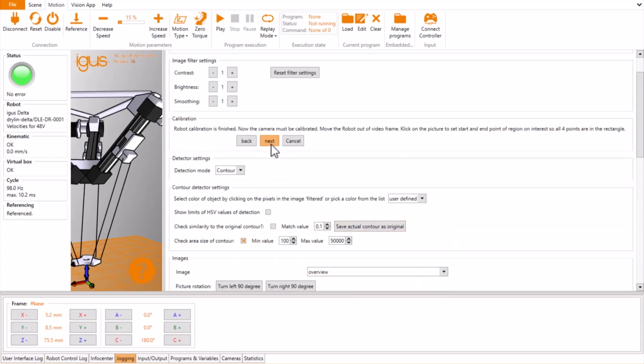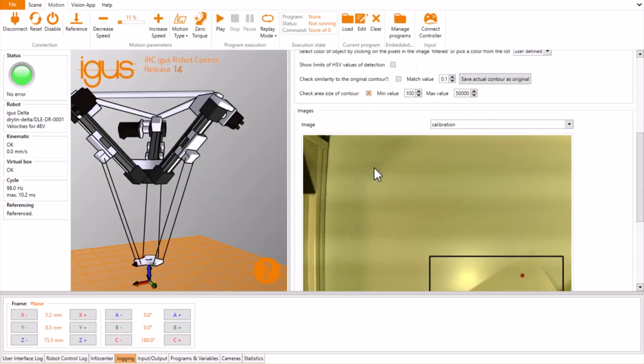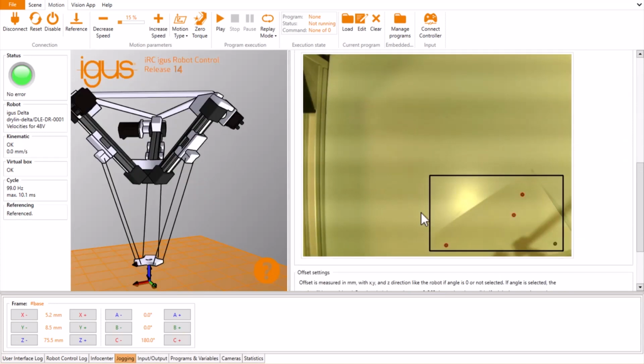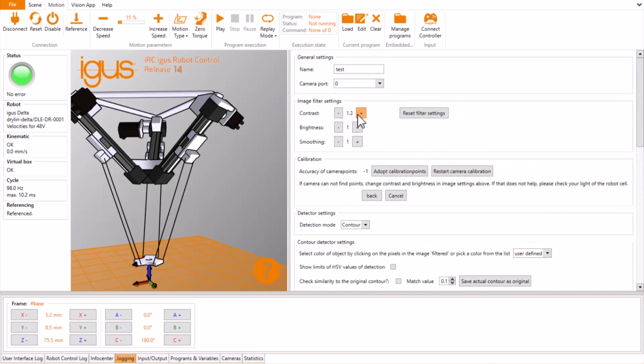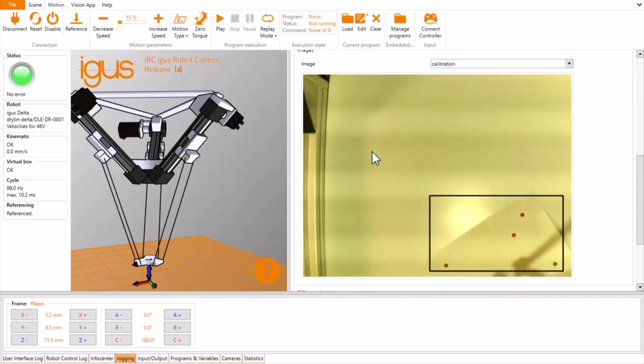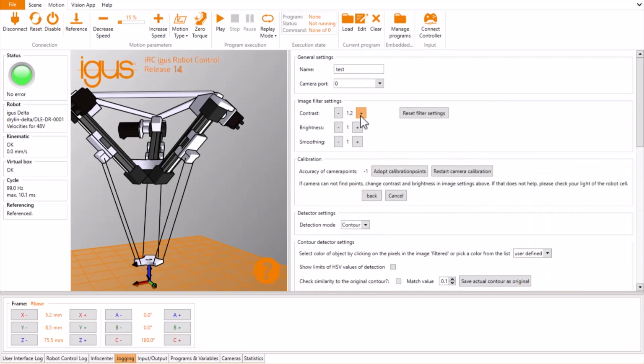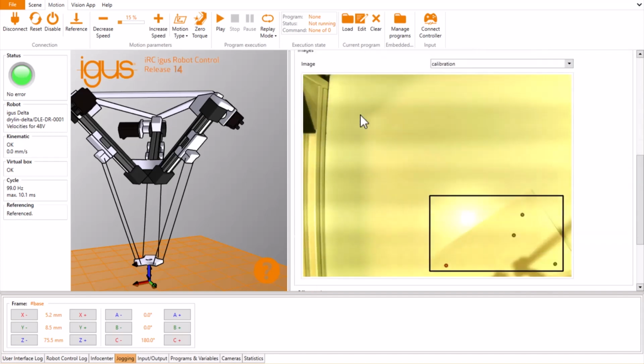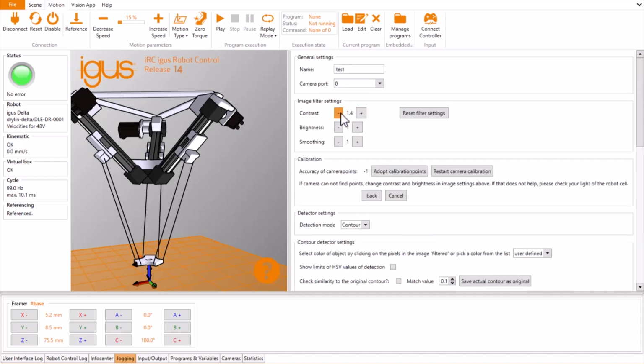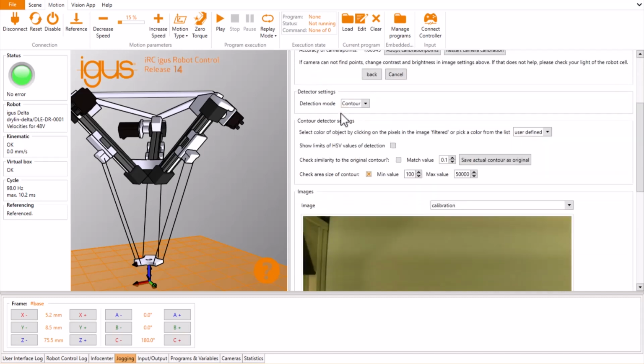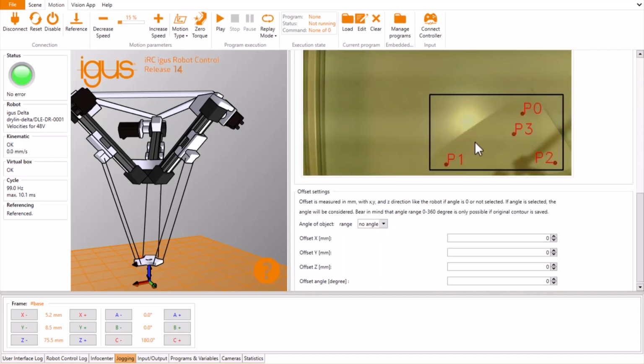The app now tries to find the 4 black dots on the camera image. When the camera has found a dot, it is initially outlined in red. You can see that the camera has already identified some of the dots, but not all of them. Use the image filter settings to change the contrast and brightness of the image until the 4 dots can be recognized. If this is not sufficient, please check the lighting. If it is too bright or too low, the dots might not be recognized without problems. In my case, the settings are now correct so that the camera has identified the 4 dots.